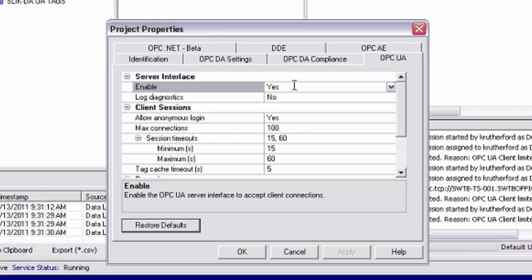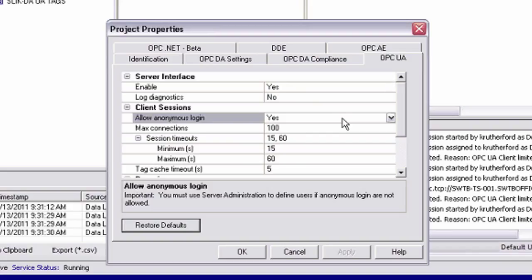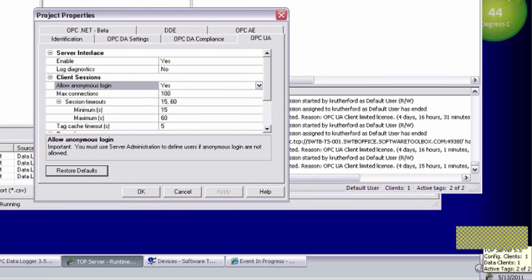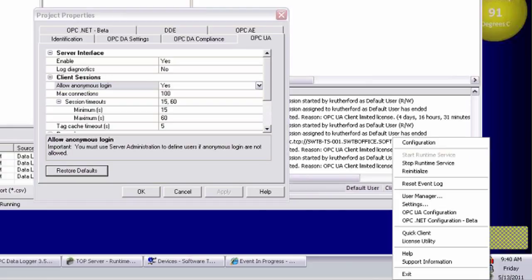If this was set to no, a UA client would never be able to connect to your top server. The other thing I want to make sure is enabled here is allow anonymous login. Since I'm not planning on using user authentication for this connection, this has to be enabled. If this is disabled, then you would have to have user and password configured, and your UA client would have to specify that making a connection.